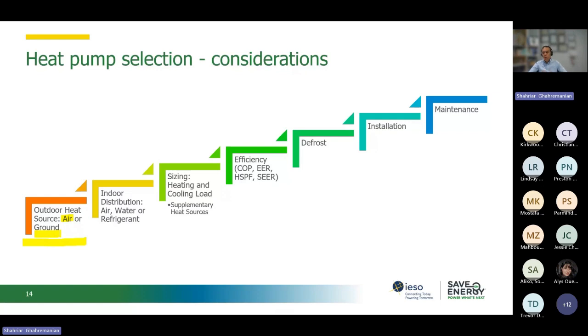So this is the first thing we need to decide. Ground source heat pumps are much more efficient, but in terms of cost, we need to drill boreholes and put refrigerant pipes down there. Down the road, the operational cost might be less compared to the air source heat pump, and it's also not going to depend on the outdoor air.